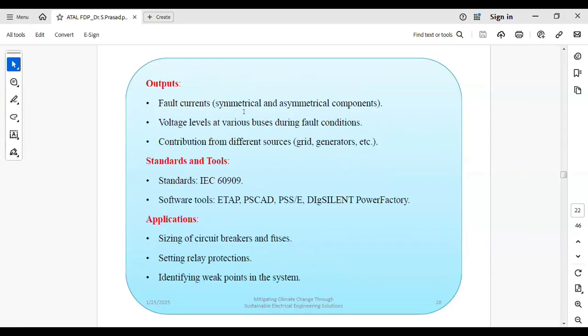So we are calculating the symmetrical and asymmetrical components of fault currents. Ik double dash we measure particularly at different buses and different feeders. This is the standard we use, and the software used is ETAP, PSCAD, PSS, DIgSILENT and PowerFactory. These are the power system software we use to conduct the short circuit analysis by referring to the IEC 60909 standard. The applications are sizing of circuit breakers and fuses, setting relay protection, and identifying weak points in the system.